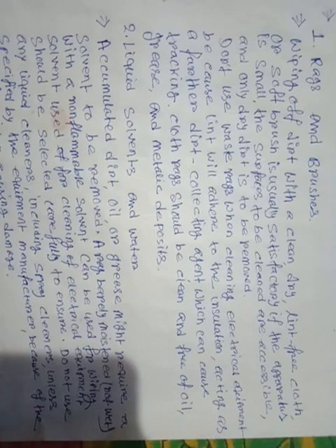Do not use any liquid cleaner, including spray cleaner, unless specified by the equipment manufacturer. When you clean any insulation material or electrical device with a liquid cleaner, there is a risk of residue causing damage. Third is vacuum cleaning.